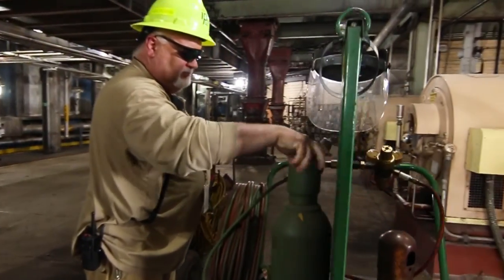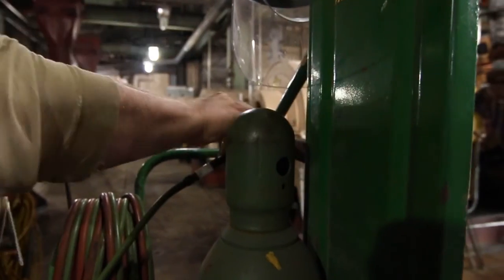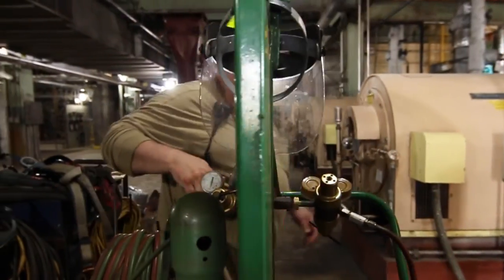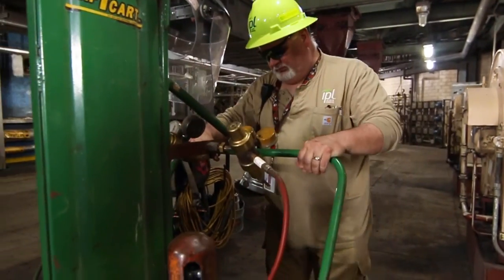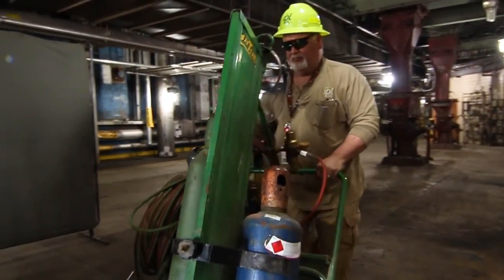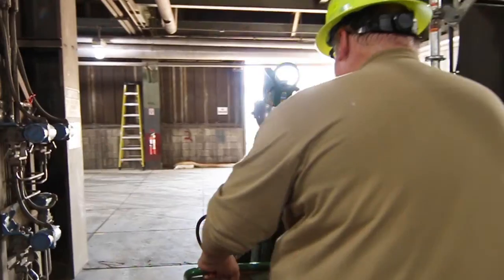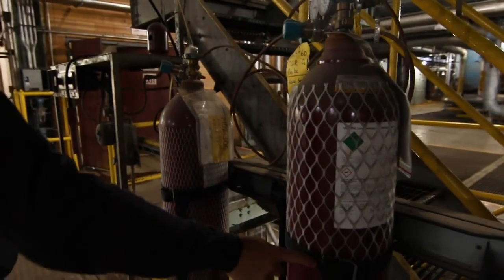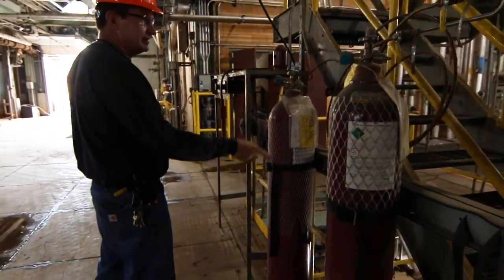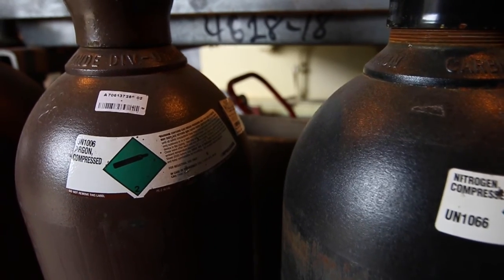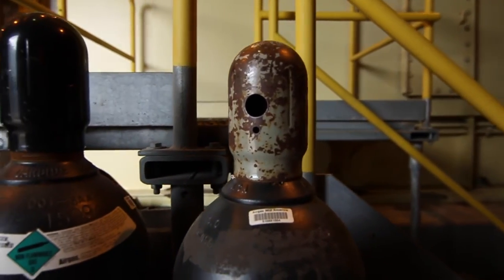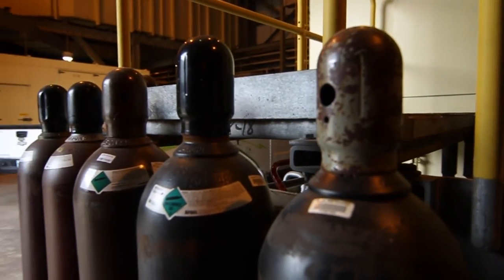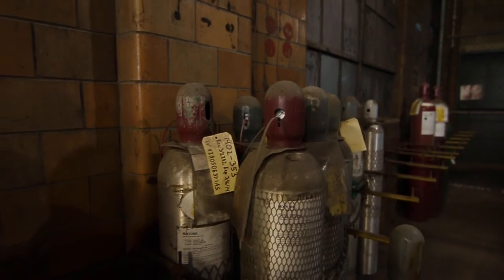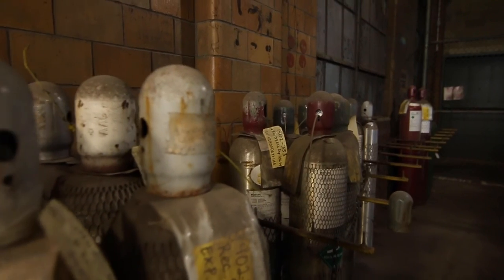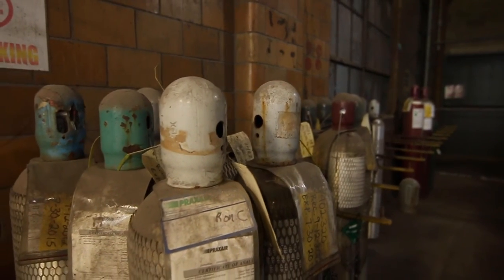When transporting bottles or carts, the regulators shall be removed and cylinders capped. If torch carts are not going to be used within a 24-hour period, they shall be stored properly by removing the regulators, capping the cylinders, and either separating the bottles by at least 20 feet or placing them within a 30-minute fire-rated barrier. All compressed gas cylinders shall be stored in an upright, secured position with regulators removed and protective valve caps in place. Compressed gas fuels and oxidizers not in use should be stored separately with a minimum separation distance of 20 feet. If fuel gases and oxidizers shall be stored together, a non-combustible barrier of at least 5 feet or 1.5 meters high, having a fire resistance rating of at least 1/2 hour, shall be used.